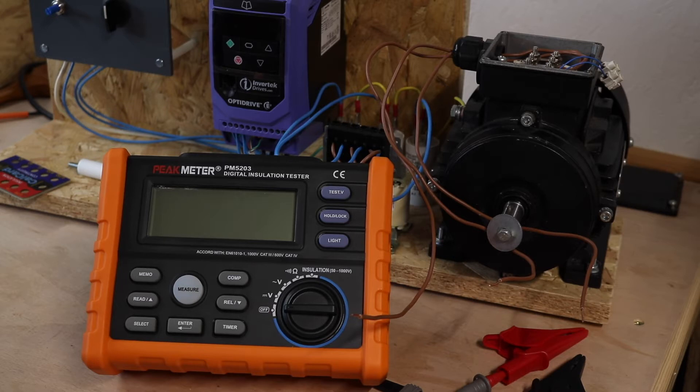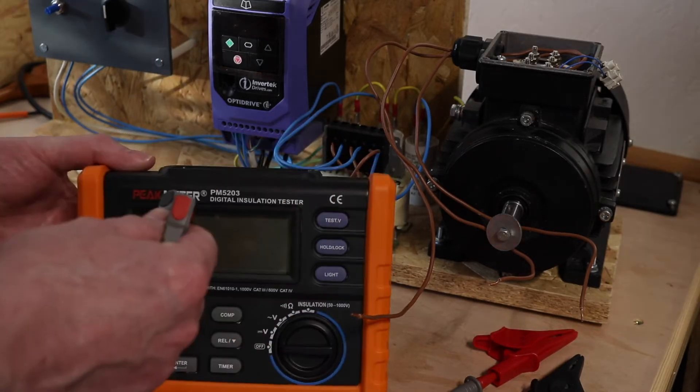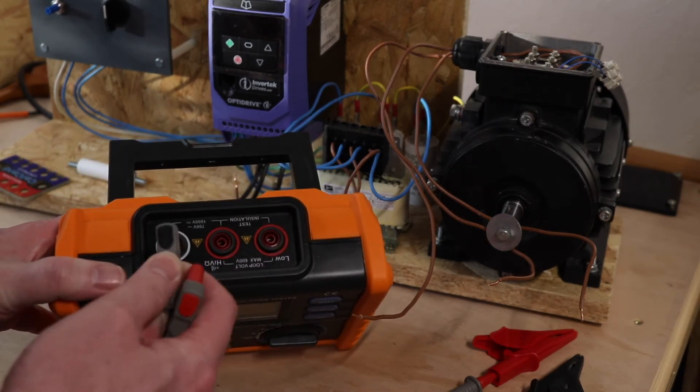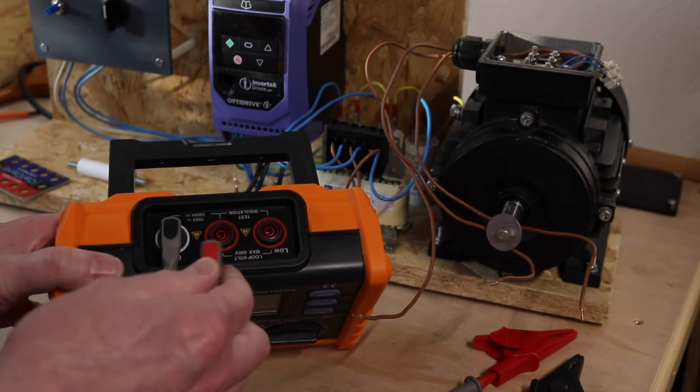I also have test results for this motor using the MTR105 that I can compare the ones from the PM5203 to. So with everything isolated, tested for dead, and then disconnected, my first test will be the winding resistance measurements.